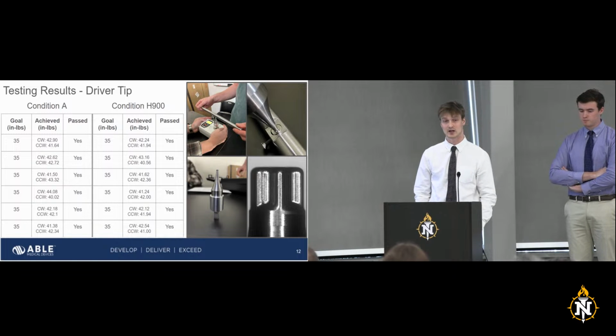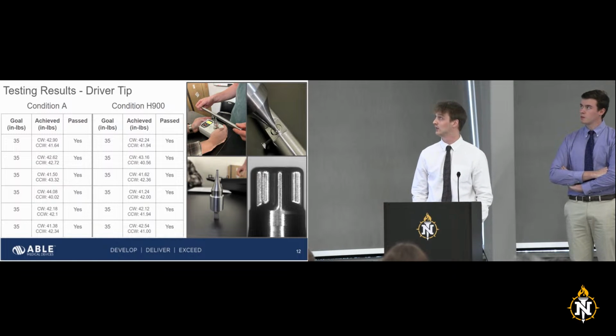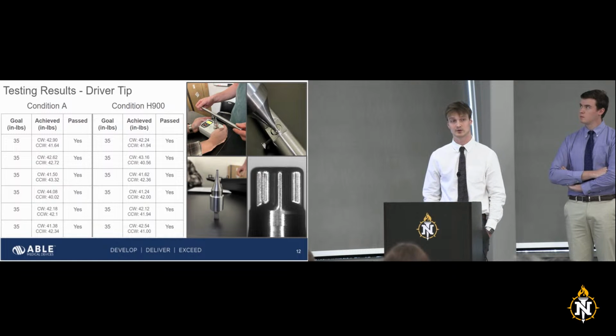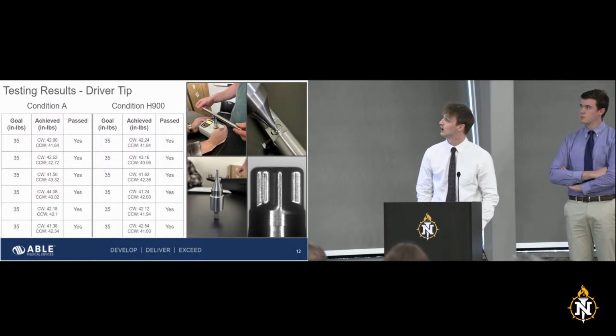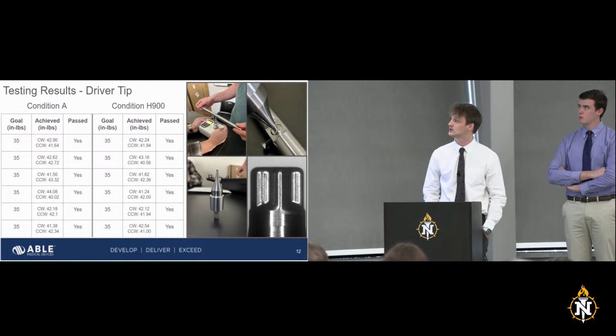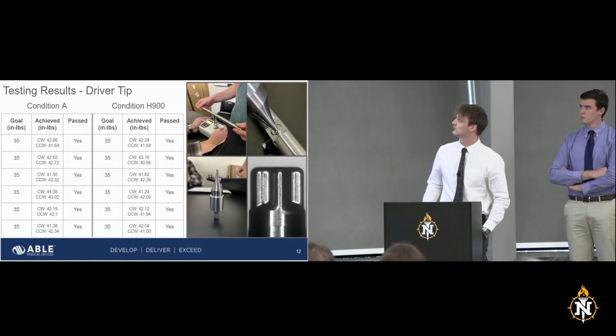We tested a condition A, the non-heat-treated version, and condition H900, the heat-treated version. We set a goal of 35 inch-pounds and achieved roughly 40 for most of these tests — all of it passed. You can also see the torque gauge in the top left photo, which had a max of 50 inch-pounds, so we didn't want to go over that and break the device.